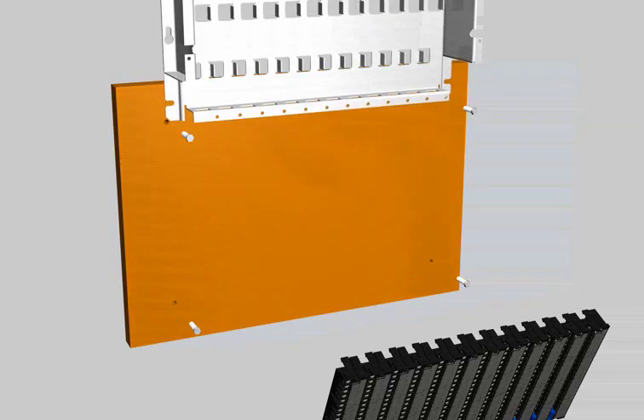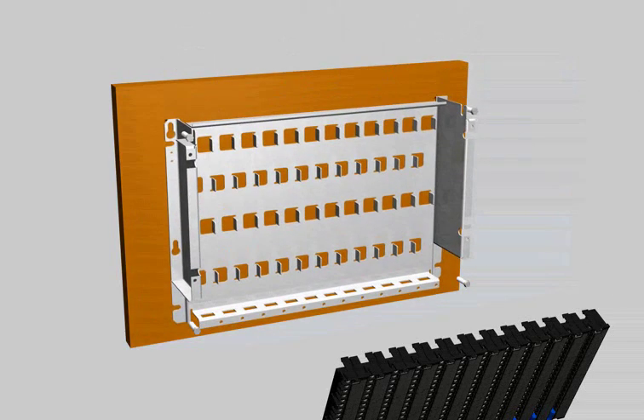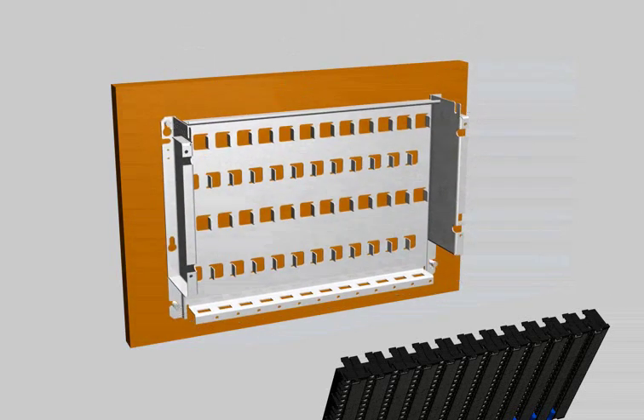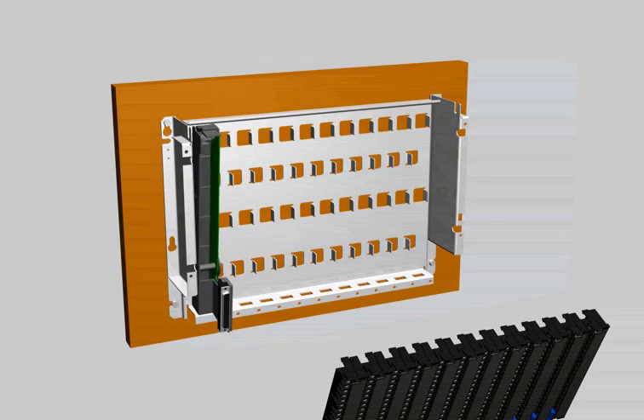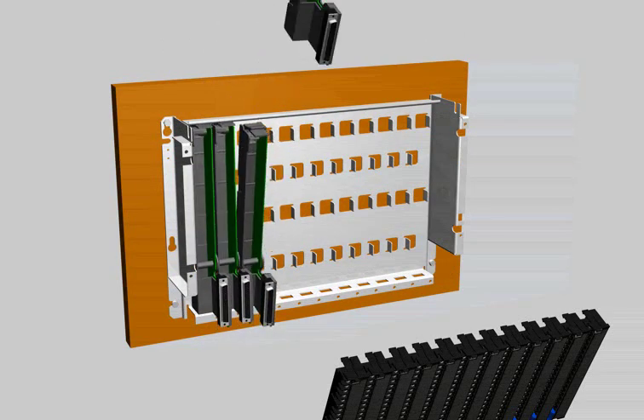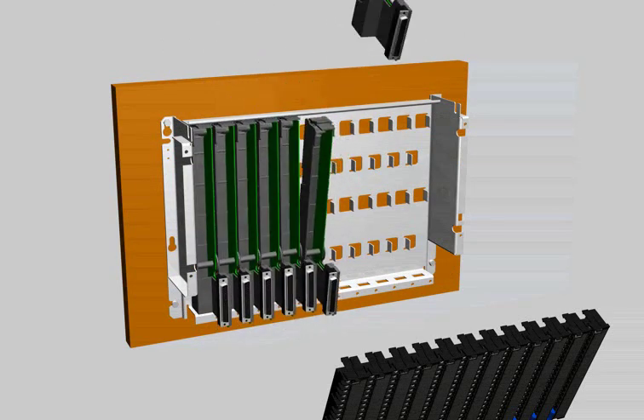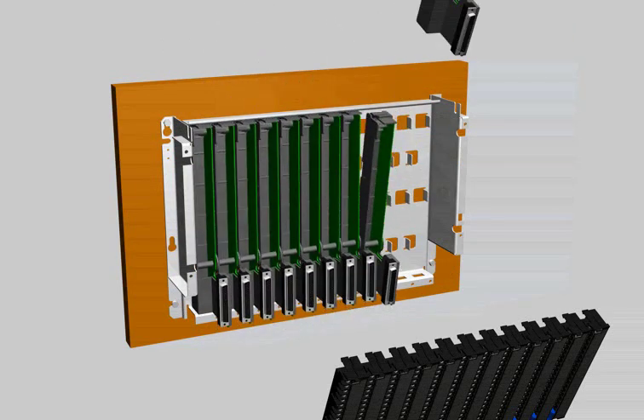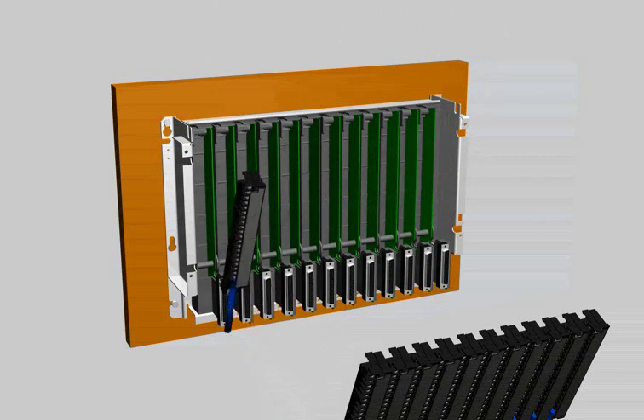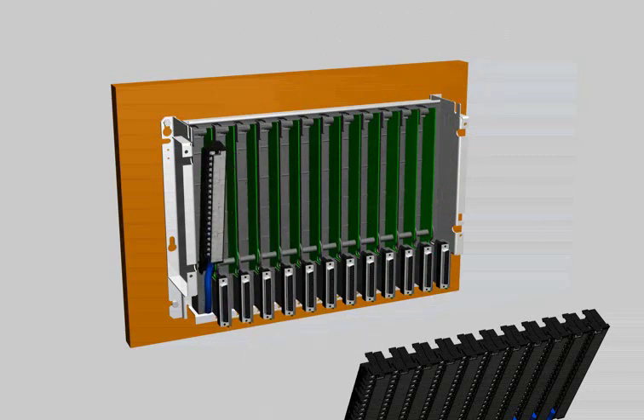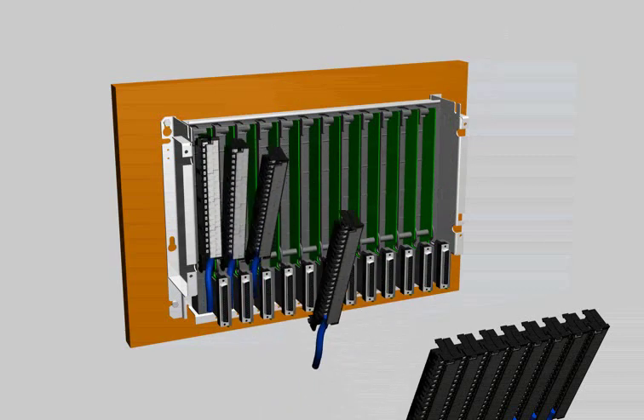Using the same screws, install the new Rockwell Automation base. Then, install our conversion modules to the base and connect the 1771 swing arm to the modules.